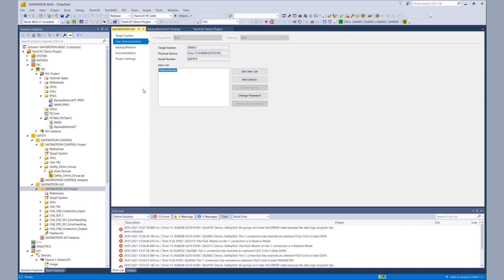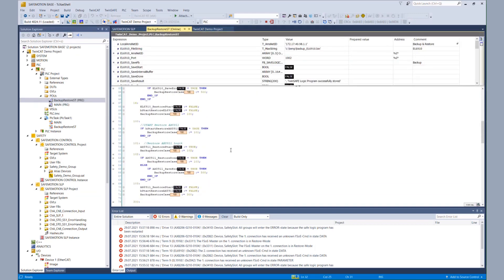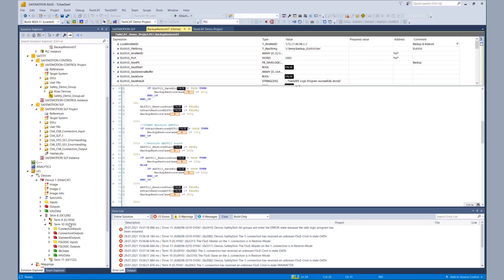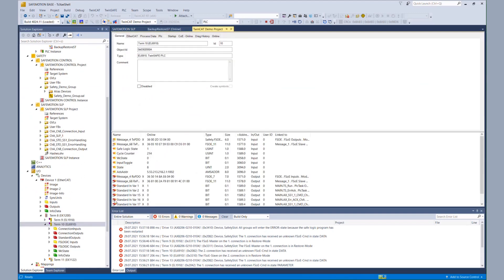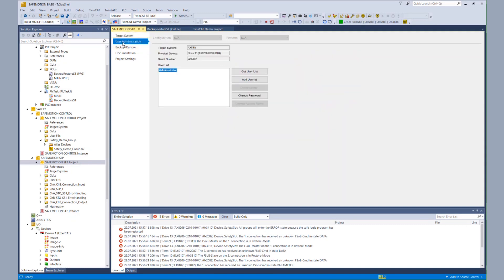Now we go back to our PLC project, and within the PLC project, we start the restore for the AX8000. The restore for the AX8000 takes a little bit longer than the EL6910. But after the download is finished, we see in the process image of the EL6910 that both connections are running again. And when we go to the target system property page and the user administration, we see that our test user was also successfully restored.